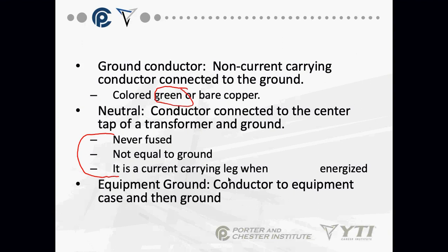We expect it. Equipment ground is otherwise known as earth ground when you're looking at the equipment - frame ground, earth ground, equipment ground, basically the same thing. It is the conductor to the equipment case and then to ground. If it has a metal case, we ground it.